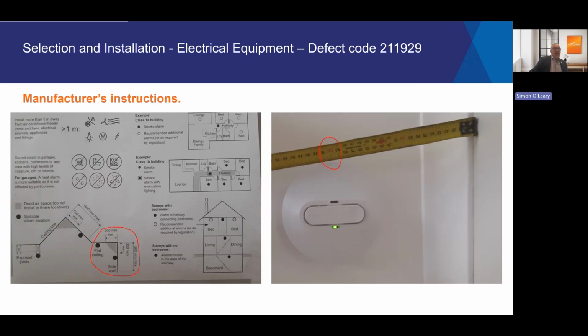Another defect that we see quite a lot of is failing to comply with manufacturers' installation instructions. In 2018, the new wiring rules put a large emphasis on complying with manufacturers' installation instructions. This is just one example of one of the defects that was identified. As you can see on the diagram on the manufacturer's installation instructions, it clearly states that smoke detectors or smoke alarms should not be installed within the 300 mil space in the corner of walls. As you can see by the photo of the actual installation, that smoke alarm is definitely within the restricted or prohibited space that the manufacturer provides.